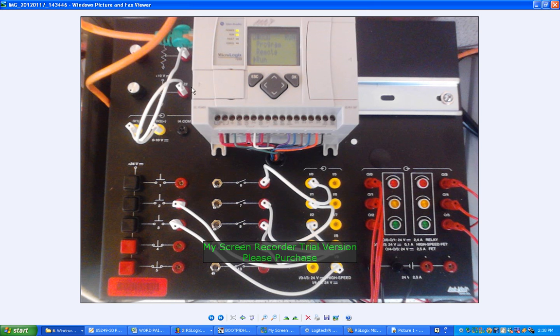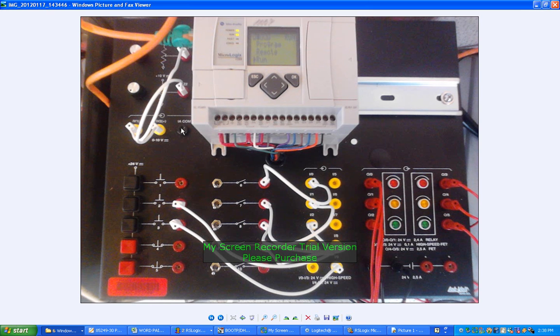And those analog inputs are going into IV1 and IV2. And it shows down here 0 to 10 volts. There's the common point. So that's your two analog inputs on your PLC.